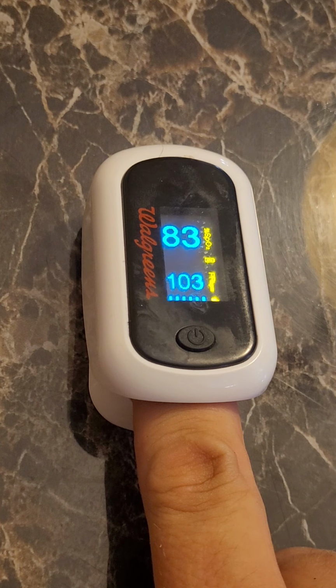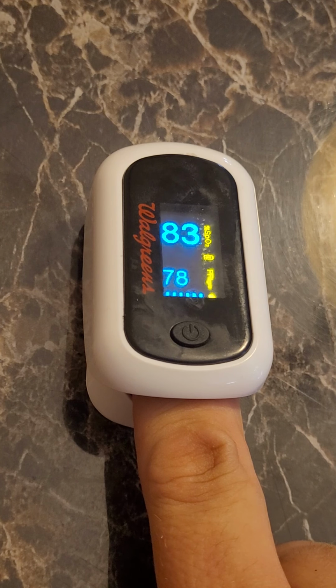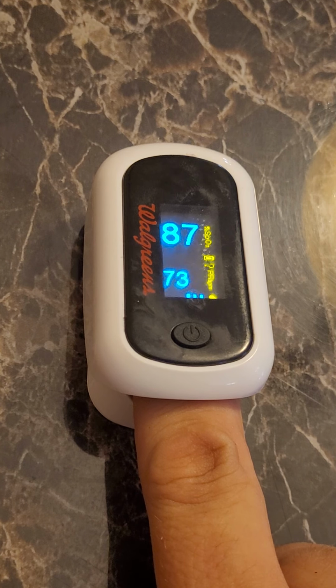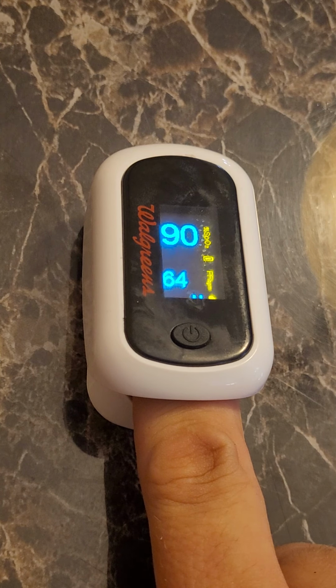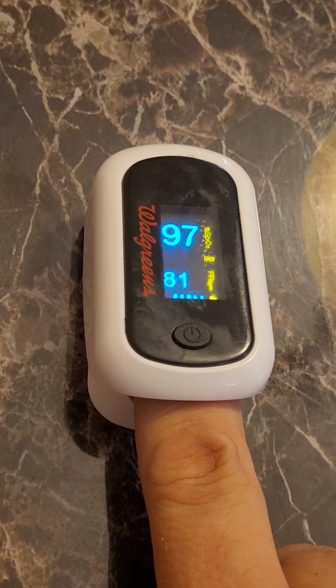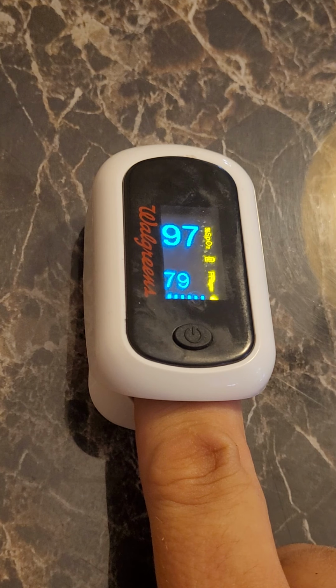So this red light, dependent upon how much hemoglobin has bound oxygen to it, can shine through a significant portion if you have a lot of oxygenated blood, or it'll have trouble shining through the darker aspects of your capillaries or veins or arteries or arterioles or venules, and you'll get a lower reading on your oxygen saturation. So this is a great example we just found ourselves with, where obviously I am perfusing adequately and I do have adequate oxygen saturation, but I'm getting a reading that's inaccurate. So give it some time, and you'll generally see your pulse oximeter start to get back to an appropriate measurement. If you're having these low measurements chronically for a long period of time, let's definitely make sure our fingers are warm and that we don't have peripheral circulation issues in whomever we're measuring the oxygen saturation of.